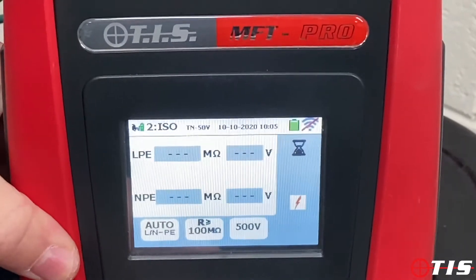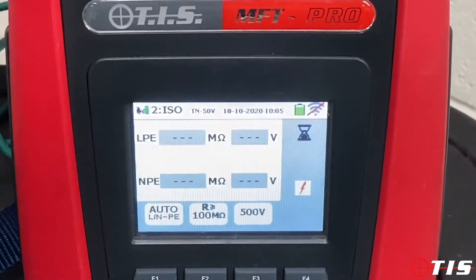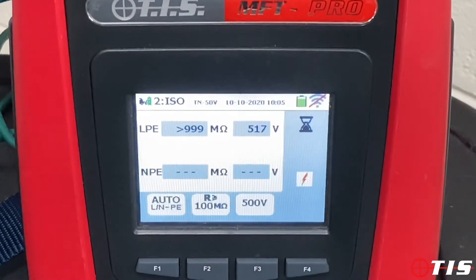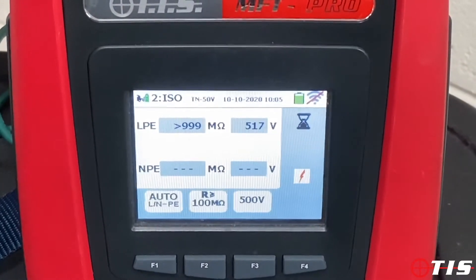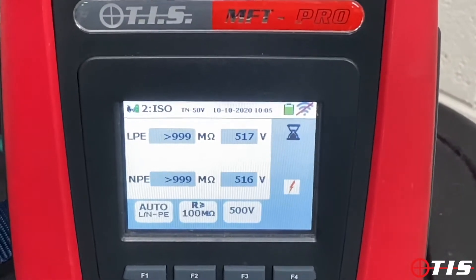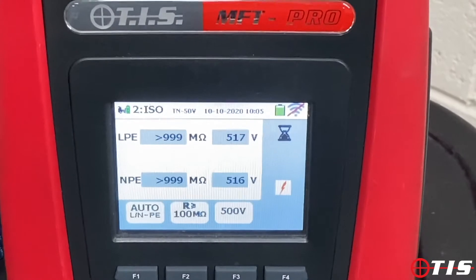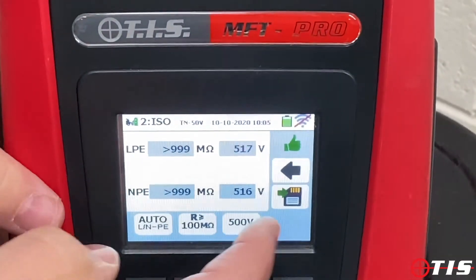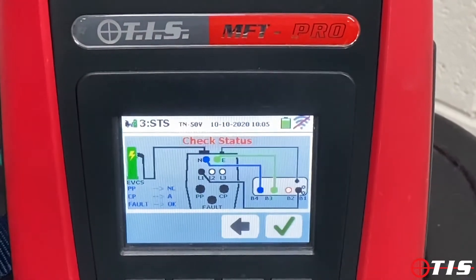It's a 500 volt insulation test. Press go and as you can see it does the full insulation test — LPE and NPE — in the push of one button. The insulation test is good, it's given me a thumbs up. Again we need to save to move on to the next status.